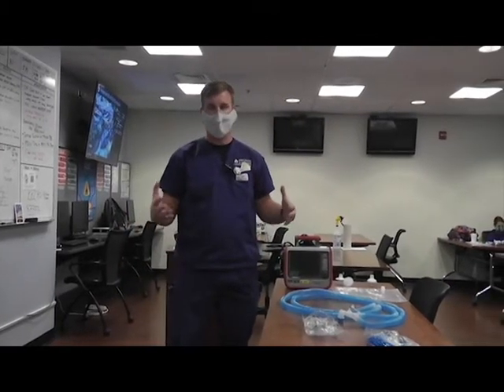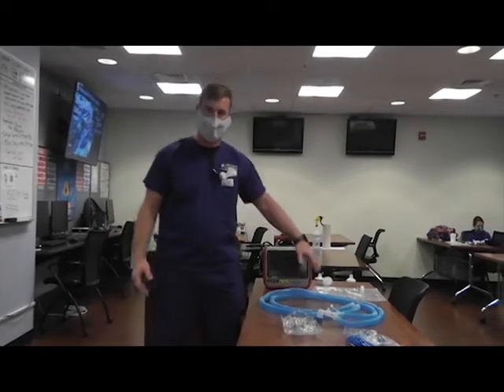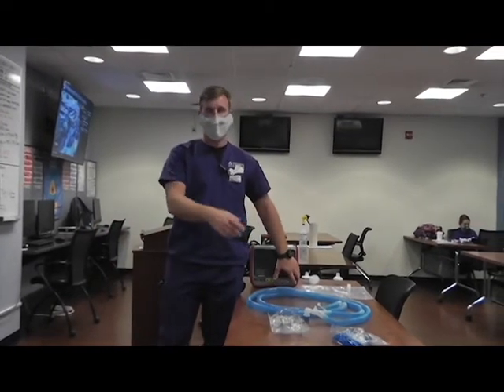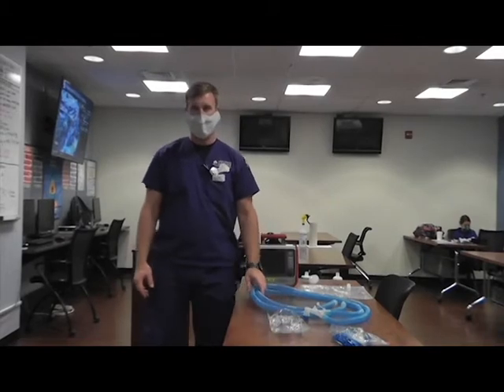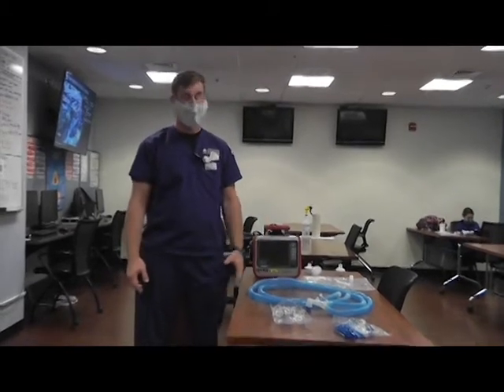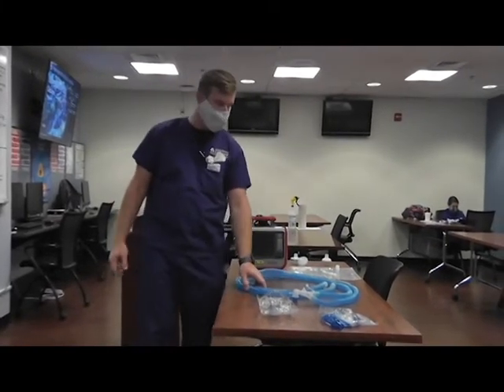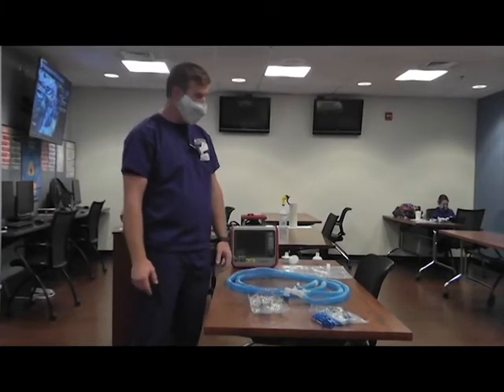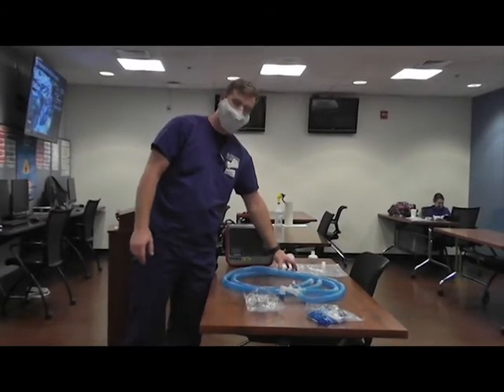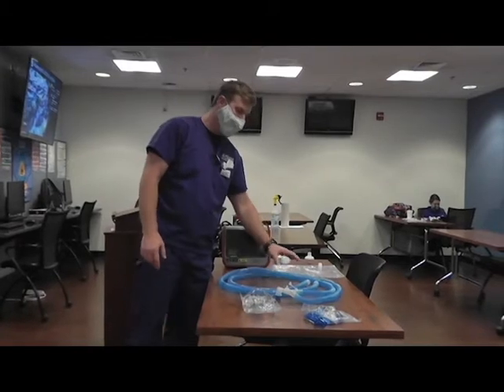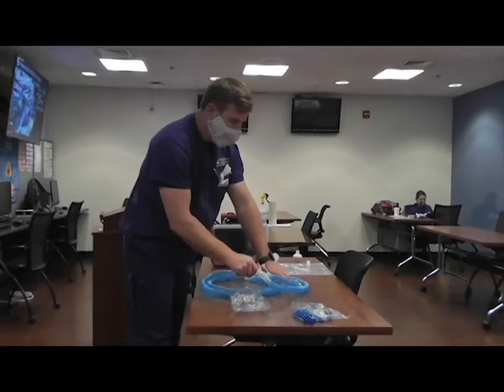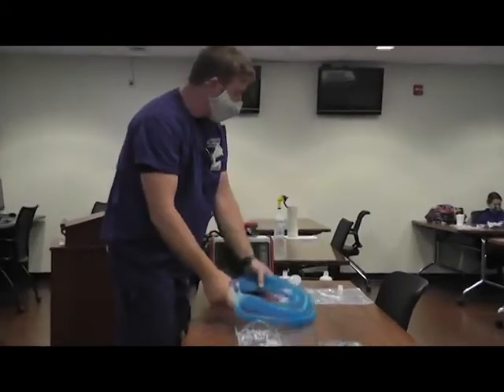The Hamilton basically doesn't care what you put between the exhalation valve and the flow sensor. You could put garden hose in between there if you want. We're not doing garden hose, we're doing this dual limb circuit here, so pretty simple. But we'll have them bagged up in two gallon Ziploc bags. You'll see the actual blue ventilator circuit.